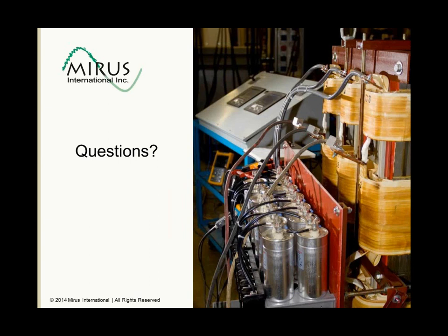Question: can these solutions be applied if you have grid supply as well as backup generators? Absolutely. This is a continuation essentially of the previous question. And it's even more important to treat the harmonics when you're operating off of a backup generator. In fact, a lot of times that's when harmonic problems appear. They may be fine off of the utility because of the stiffness of the utility system, and there's not that much distortion that results. But as soon as you switch to generators, the voltage distortion goes up dramatically because of the high impedance of the generator.